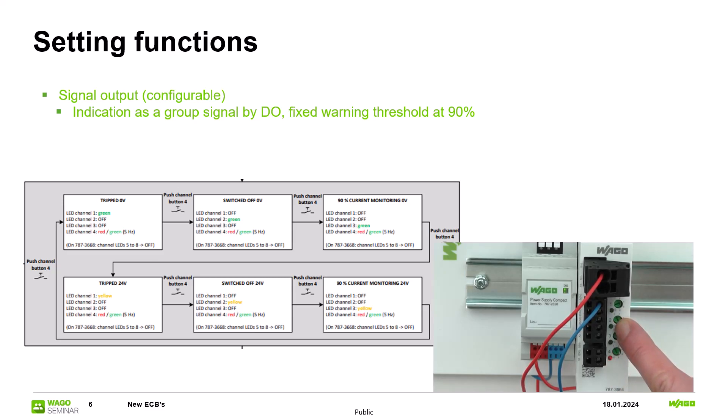If the channel number 2 lights up green the digital output is pulled to 0V if the channel has been tripped or switched off. If the third channel indicates green the digital output is triggered when 90% of the current value setting is reached.